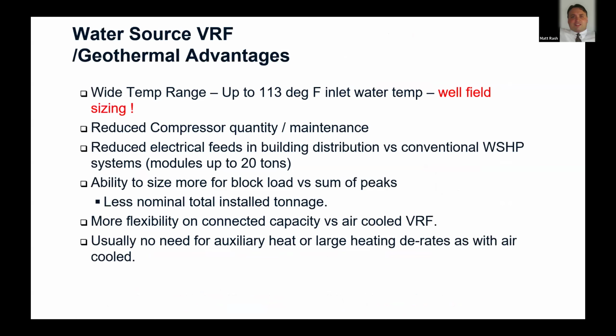So again, some of the bigger advantages with water source VRF, and this isn't necessarily exclusive to this type of technology, include a wide temperature range up to 113 degrees. Like I mentioned, this can play into well field sizing. It reduces compressor quantity and maintenance because we don't have to have individual zoned water source heat pumps. To provide an equivalent level of zoning, we can reduce the number of electrical feeds and number of points of maintenance, and really get the compressors outside of the occupiable space in most cases. So there's ease of maintenance and reduced electrical feeds from main switchgear or panels. Again, we offer single module units up to 20 tons. I didn't mention that before, but above that you start twinning modules together.